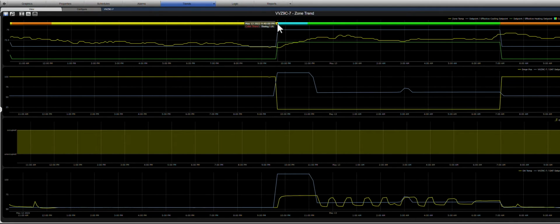sometime at, let's see, 9:40 p.m., perhaps a shift change, someone came in and said, nope, I want this space to be maximum heating rather than maximum cooling. So they changed that, and of course we very quickly drifted into the green band, or heated it. We should have a hot water valve, but we don't have one here. Let's just add the hot water valve quickly.